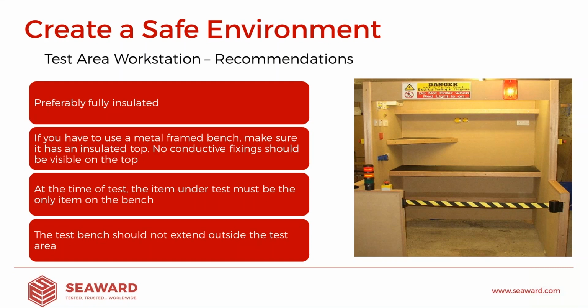And the first thing to consider is the test bench itself that you're going to use. Now, ideally, you would want a fully insulated test bench. You can see in the example on the picture that the test bench itself is all made of wood. Wood is non-conductive, so that would be absolutely ideal. It may not be possible to have a wooden bench. It may be that you're already working with a certain environment and you may have to use things like metal frame benches, in which case we should certainly consider insulating the top of the bench, the area in which the product and the test equipment will sit when we're performing the test.